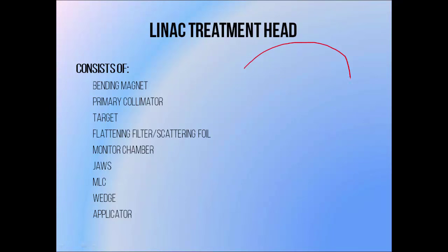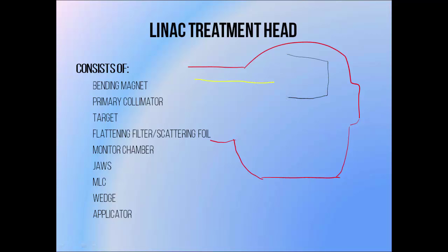When the high energy electron beam exits an accelerating waveguide it's generally not pointing at the patient — it's moving parallel to the floor. The first component of the treatment head is a bending magnet which points the beam towards the patient. Below this is an x-ray target which can be put in the way of an electron beam if we want to turn it into a photon beam, or pulled out of the way if we want to treat with an electron beam instead.